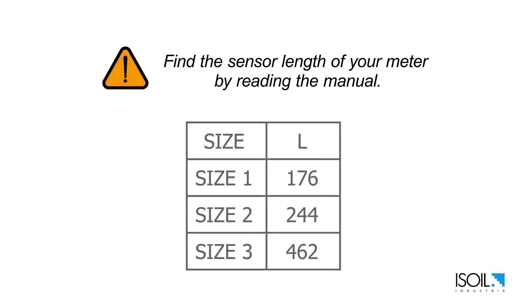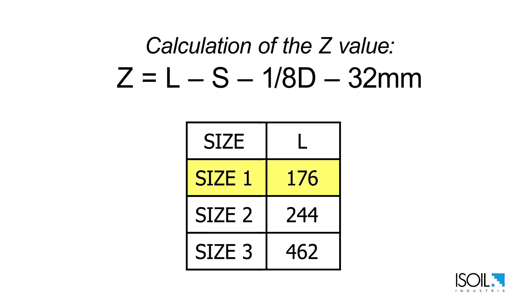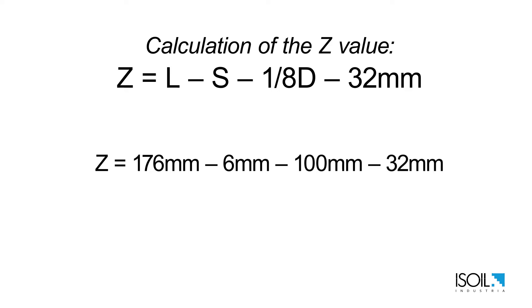Now we can calculate the Z value. Take the sensor length of your meter defined by its size. You can read it in the manual. In this case it is 176 millimeters minus the S value 6 millimeters minus 100 millimeters of insertion length, minus 32 millimeters of sensor nut, giving a total Z value of 38 millimeters.